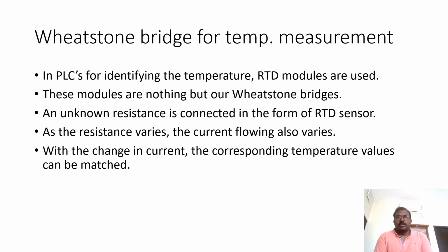In PLCs, we have RTD modules. These modules are nothing but Wheatstone bridges. These RTD modules are used for measuring the temperature of, say, steam, water, or a liquid, or a specific area. This RTD sensor is connected to the terminals of the RTD module.